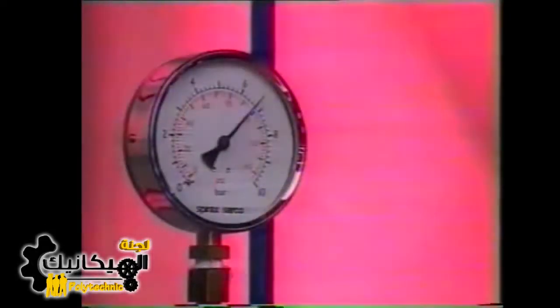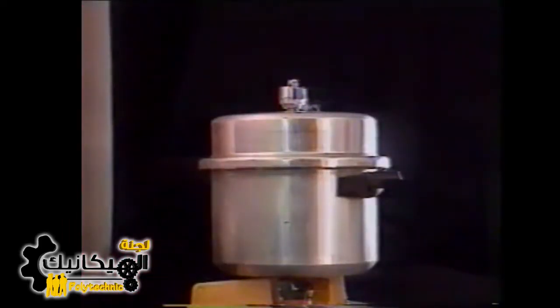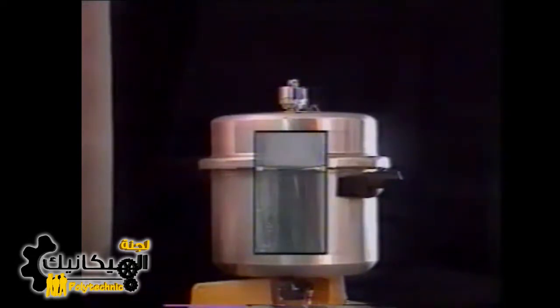One, the steam bubbles within the main boiler water expand under the reduced pressure, causing the surface level to rise. And two, at the same time, water flashes into steam, resulting in more turbulence. Flash steam occurs whenever there is a lowering of pressure. If you had a vessel containing high-pressure water just below its boiling point and opened a valve to lower the pressure, some of the water would spontaneously change to steam without any heat being supplied.